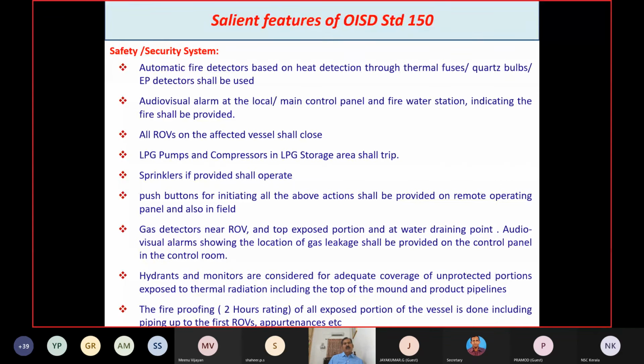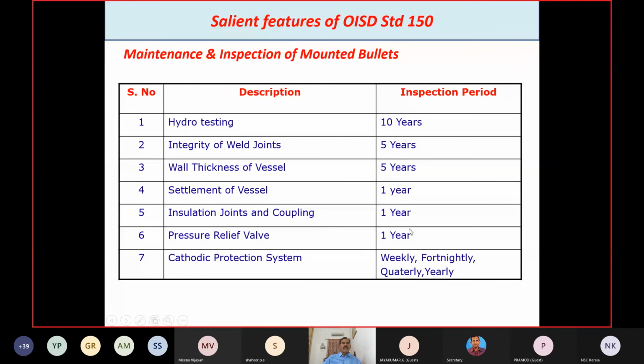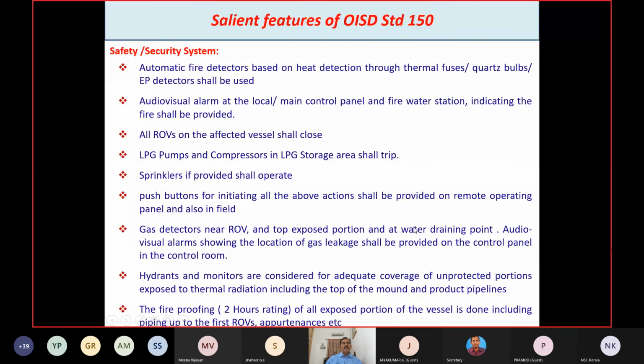Gas detectors near the ROV, at the top exposed portion, that is the top end, and at the water draining point should be provided. Audio-visual alarm showing the location of gas leakages shall be provided on the control panel in the control room. The hydrants and monitors are considered for adequate coverage of unprotected portions exposed to thermal radiation, including the top of the mound and product pipelines. Then the fireproofing, this is passive fire protection: fireproofing with 2 hours rating of all exposed portions of the vessel is done, including piping up to the first ROV, appurtenances, etc.